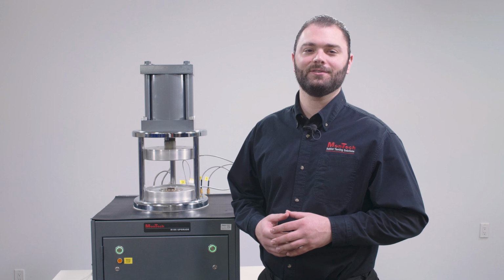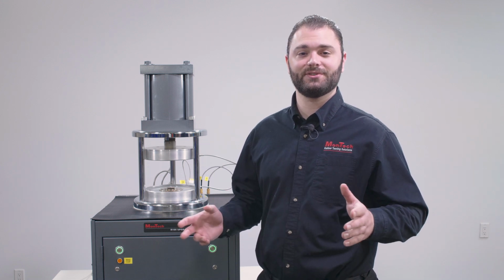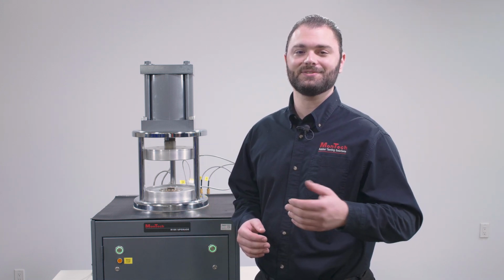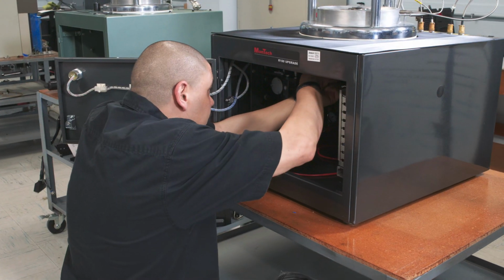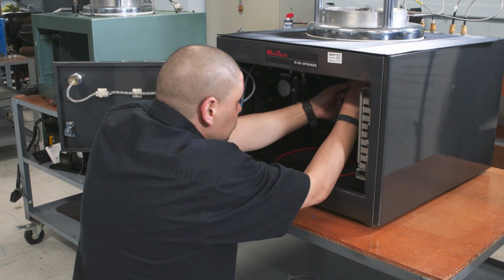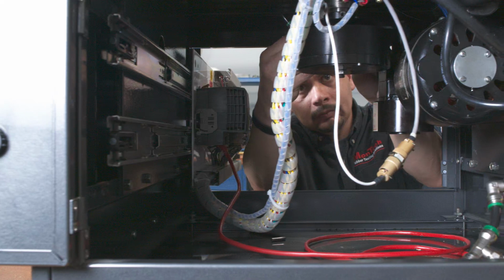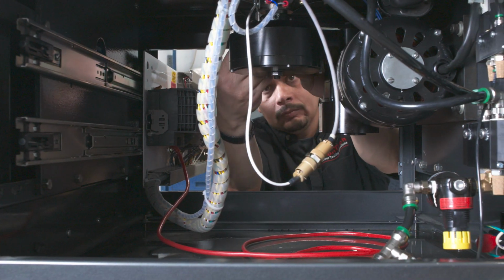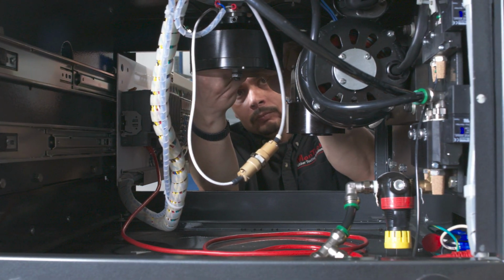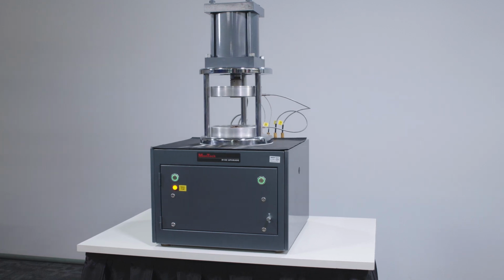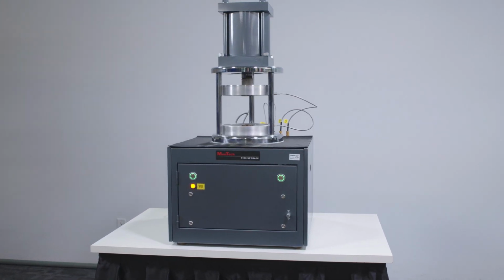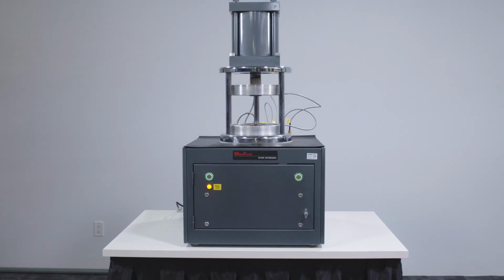MonTech upgraded R100 is the ideal budget-friendly solution for updating legacy oscillating disc rheometers. Installed by skilled technicians in our ISO 17025 accredited facility, each MonTech upgraded R100 is completely restored with over 70 new and refurbished components. Each machine is completely disassembled, glass bead blasted, cleaned and repainted inside and out.